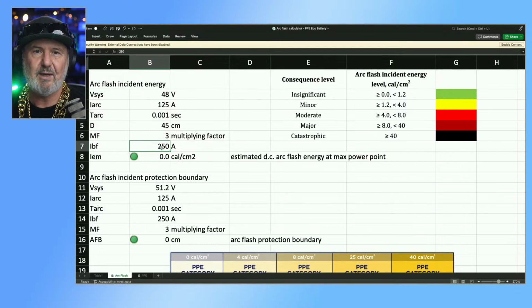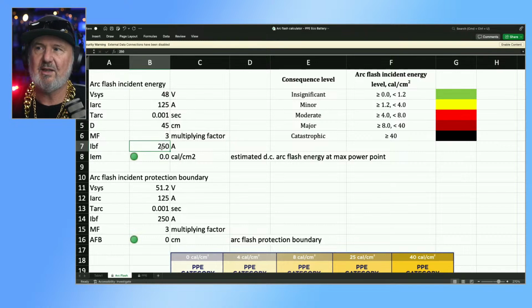So in the case of a lead acid battery, the most positive and negative terminals, you put a nice big copper bar across there, and what is the fault current? Now, I don't do that. Please do not do that. What you do is you go to the manufacturer and ask them what is their maximum fault current. It can be expressed in milliohms per cell, and you can just divide the cell voltage by the milliohms per cell to calculate the current.